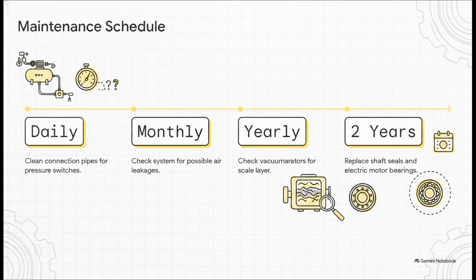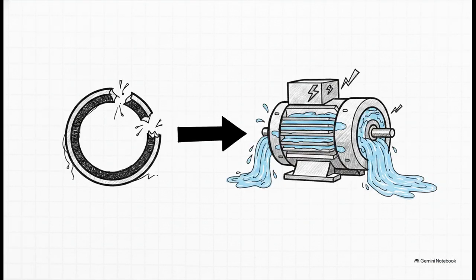Every 2 years, or 6,000 working hours, you are scheduled for a major overhaul to completely replace the crucial shaft seals and electric motor bearings. We hammer these timelines home because we're not just telling you to check for scale layers for the fun of it, right? Ignoring this protocol has severe, expensive consequences. If you fail to replace those shaft seals at the 6,000-hour mark, you are practically guaranteeing water leakage directly into the motor. So instead of a routine afternoon replacing a worn seal, you're suddenly dealing with an entirely destroyed, flooded 20-kilogram machine, and trust me, a very messy situation on board.